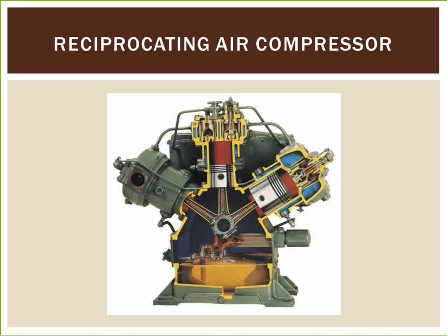For reciprocating air compressors, they are positive displacement machines, meaning that they increase the pressure of the air by reducing its volume. This means they are taking in successive volumes of air, which is defined within a closed space, and elevating this air to a higher pressure. The reciprocating air compressor accomplishes this by a piston within a cylinder as the compressing and displacing element.